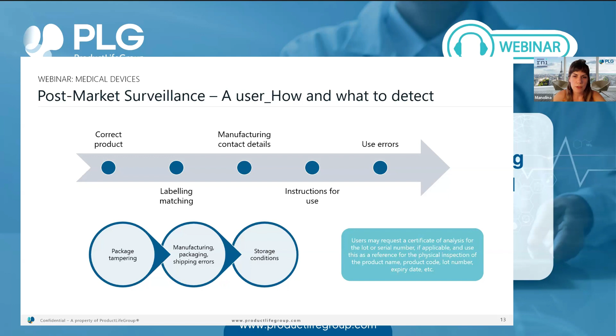So about now the system of post-market surveillance, which is necessary for all the medical devices, is a combination that can give us information for the post-market surveillance, the post-market clinical follow-up that we will see later, and the vigilance of the medical devices. These activities should be carried out by manufacturers in cooperation with other economic operators. They should proactively collect and review the experience gained from the devices, and also actively and systematically gather, record, and analyze relevant data, so they can keep the quality, performance, and safety of the device throughout its whole entire lifetime.